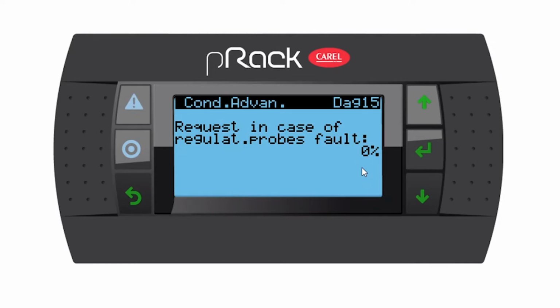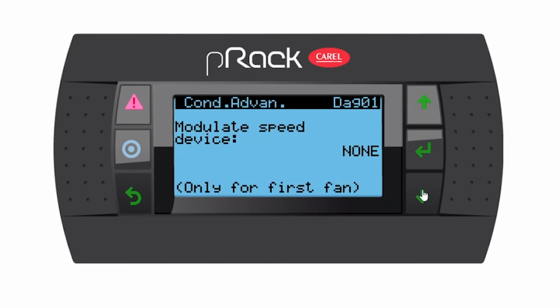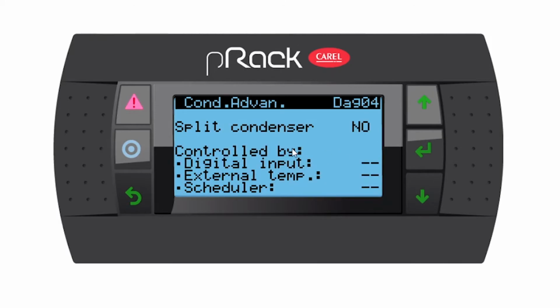I would go for the 75 if I have electronic EEVs, which will still regulate a perfect superheat. If it's thermostatics, I would rather run on the higher side, so I'll put this on 50. So that's where you're going to set this percentage on. So for here, I'm going to say let's run at least 2 fans and go down. Modulating speed device, none. And then we're back at the beginning.